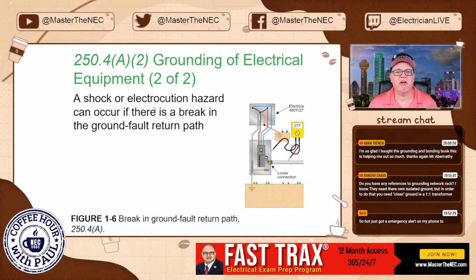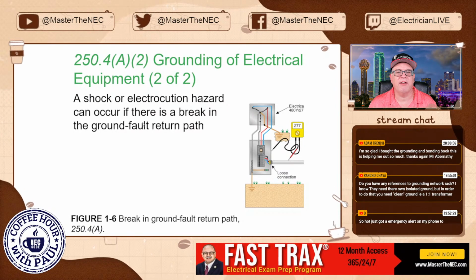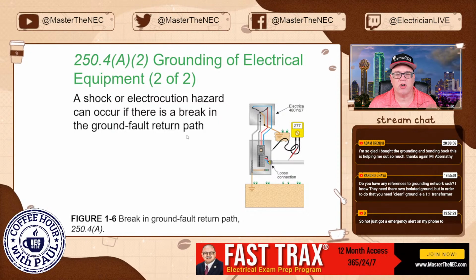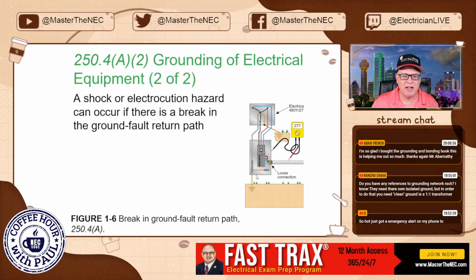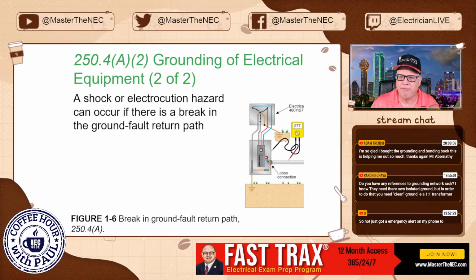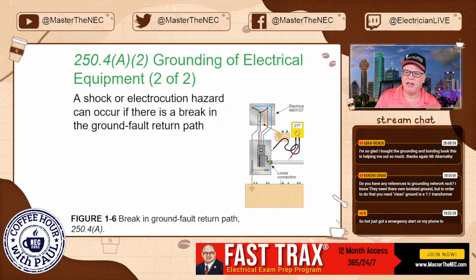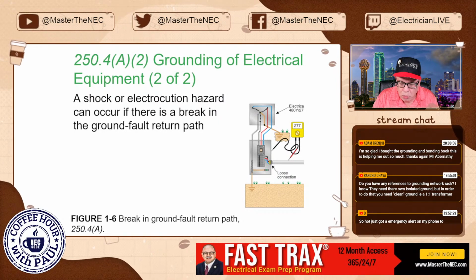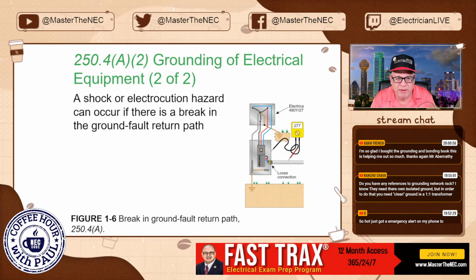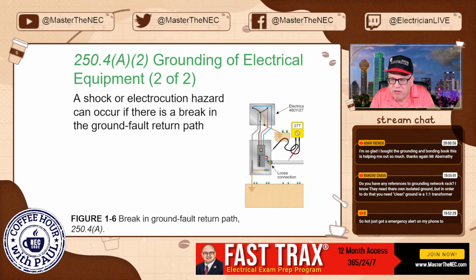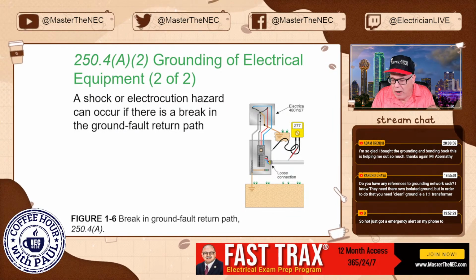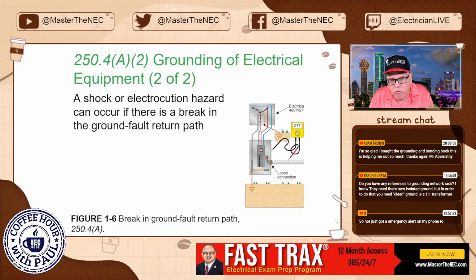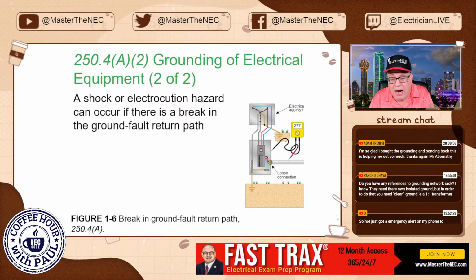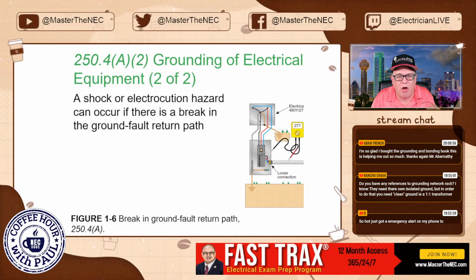250.4(A)(2): a shock or electrocution hazard can occur if there is a break in the ground fault current path. We've probably seen an illustration of this before, but this illustrates what happens and why we do what we do prescriptively through the code. Why we make sure that things are wrench tight, why we run things the way we do, why we make sure our couplings are done right, and all this type of stuff.